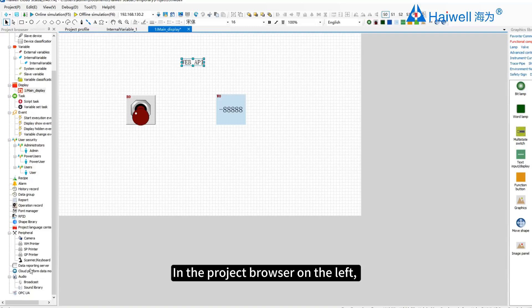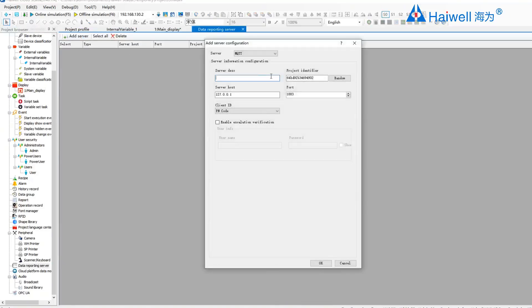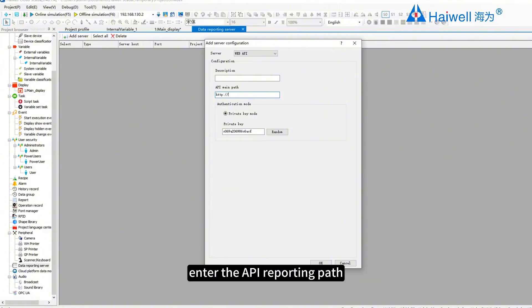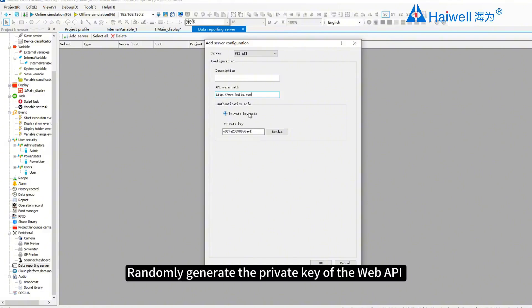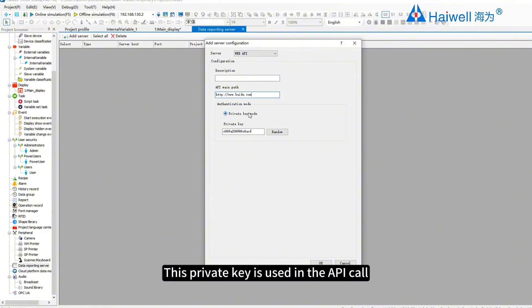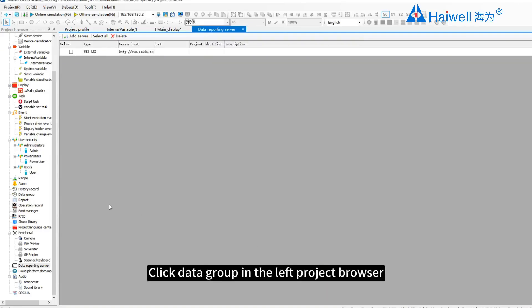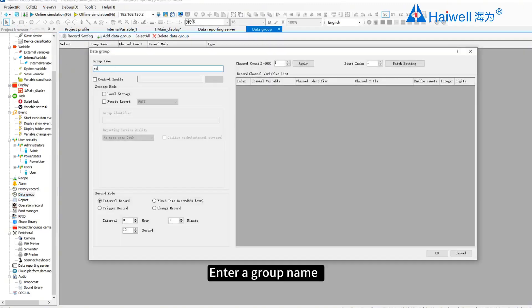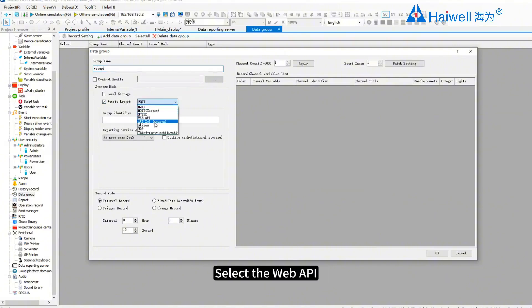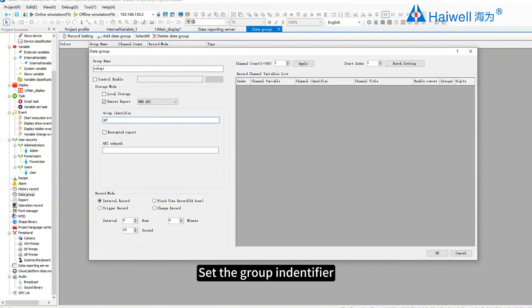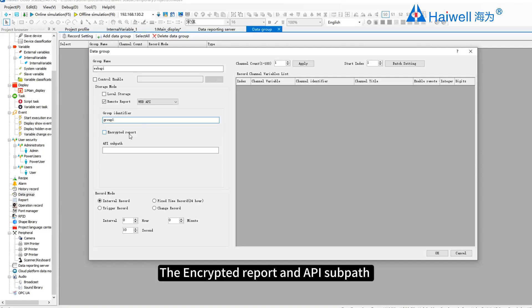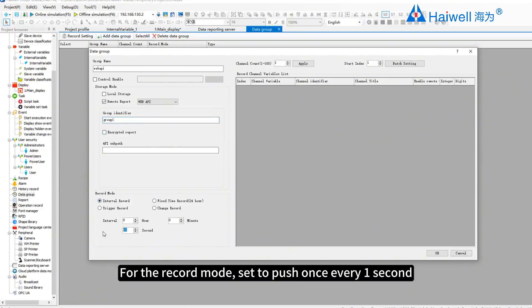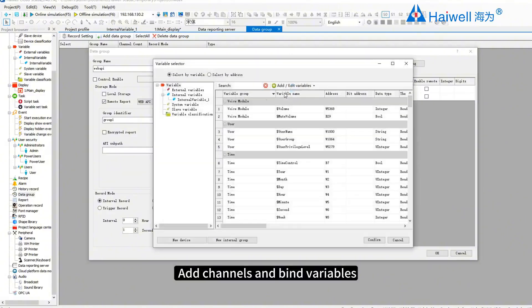In the project browser on the left, click Data Reporting Server and select the server. The server selects Web API. If the data needs to be reported to the server, enter the API reporting path and randomly generate the private key of the Web API — this private key is used in the API call. Click Data Group in the left project browser and select to add a data group. Enter a group name, select Remote Report, select Web API, set the group identifier. The encrypted report and API subpath can be configured as required. For the recording mode, set it to push once every one second, then add channels and bind variables.